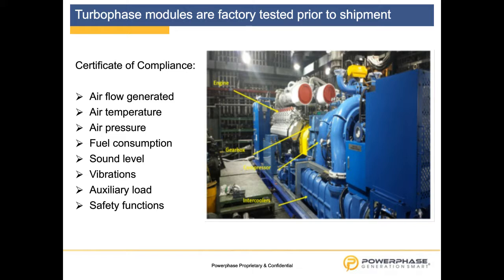At site it is just put onto the foundations, into the place where it has to be, and connected to the pipes that we have already installed during the lead time of these modules. That means that the real commissioning time of that Turbophase module is less than a week from arrival to site. That is possible because the installation, the airflow, the pipes and all components and interfaces on site that I have mentioned before will be done in advance, prior to the arrival of the Turbophase module.